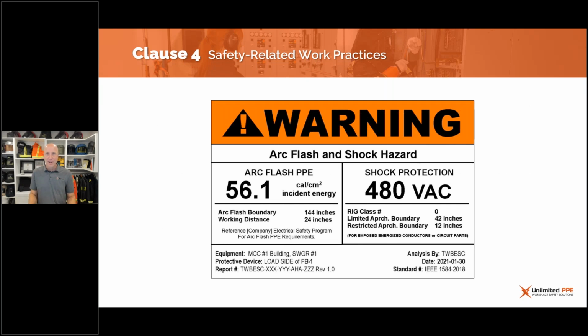That's a myth offline about that. The old category selection method was capped at 40 calories. That's one reason why I believe there's this myth embedded in our industry that you can't work above 40 calories. Another reason is this belief that arc blast will kill the worker if they're exposed to anything greater than 40 calories. That's also a myth.